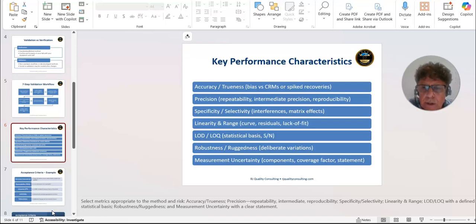In your method validation, you should be defining what your measurement uncertainty is, and how you were able to generate that measurement uncertainty with 95% confidence that you agree that your results are correct with a k factor equaling 2. Measurement traceability and measurement uncertainty sort of go hand in hand. It is within the method validation that you determine what your measurement uncertainty is.